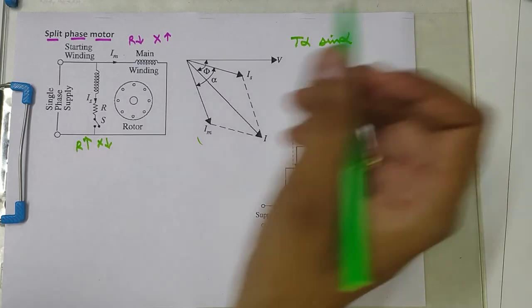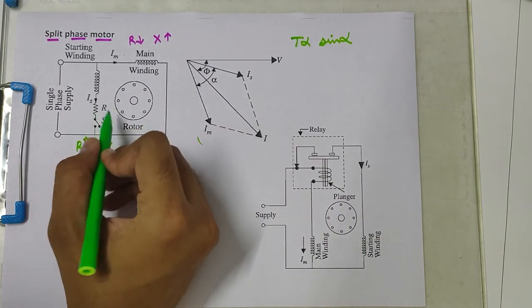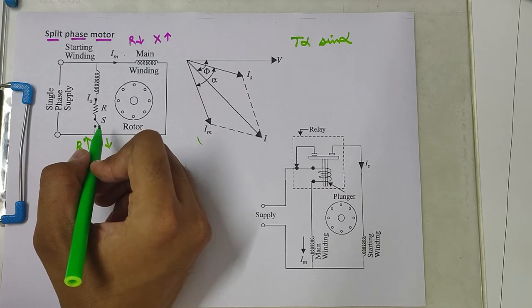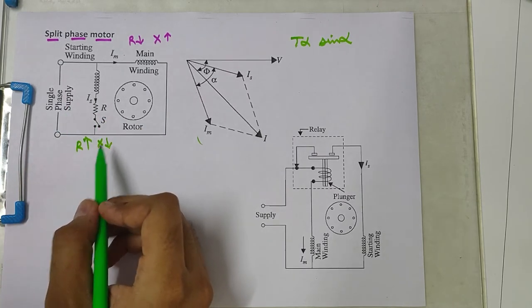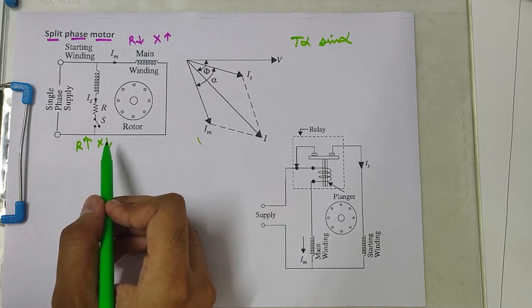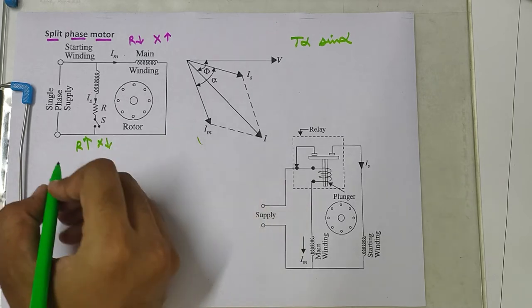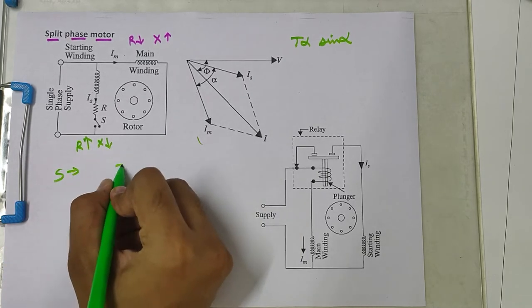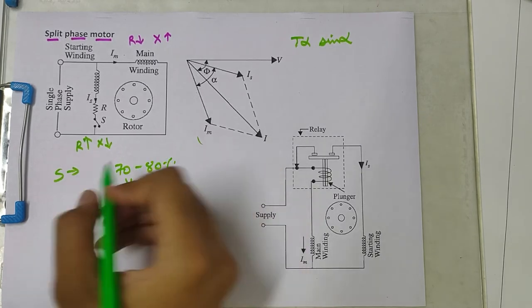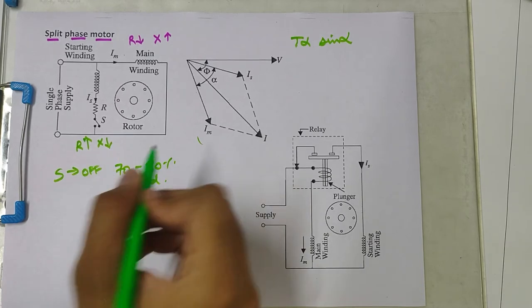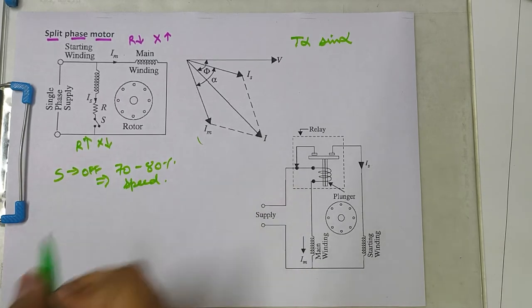A centrifugal switch is connected in series with the winding and is located inside the motor. Its function is to automatically disconnect the winding from the supply when the motor reaches up to its 70 to 80% of speed. So at 70 to 80% of speed this switch will be off.